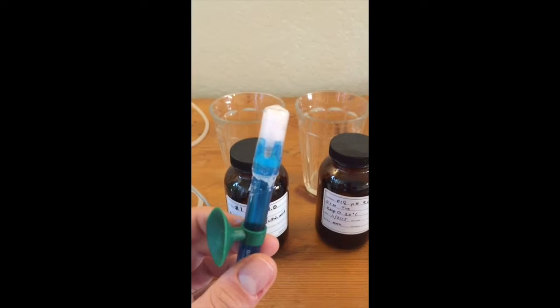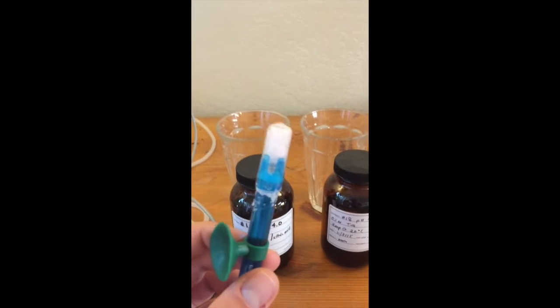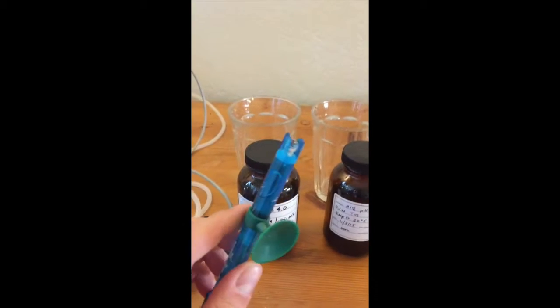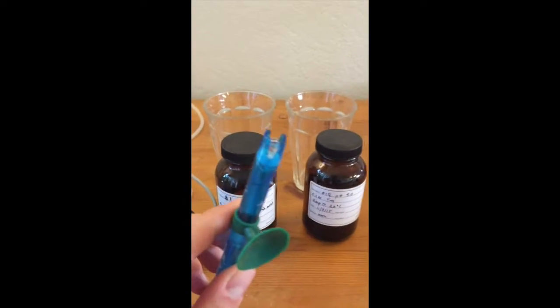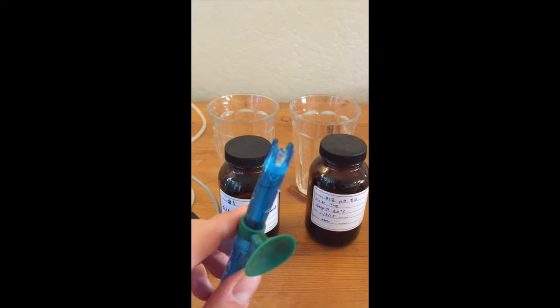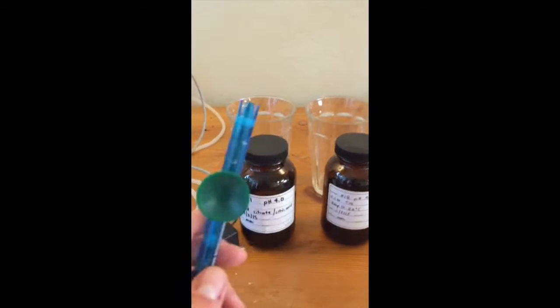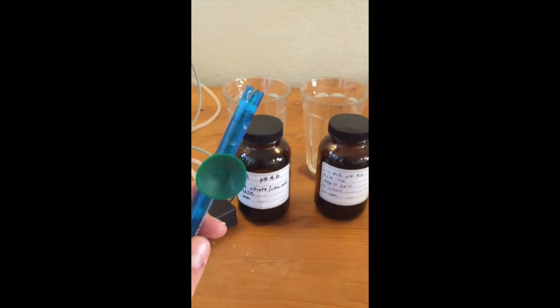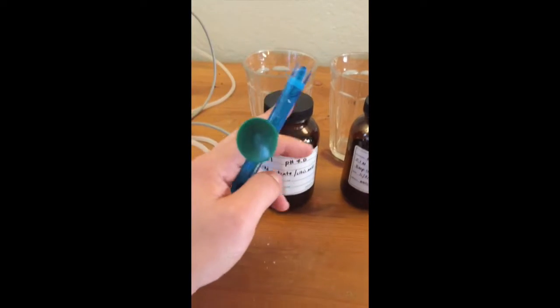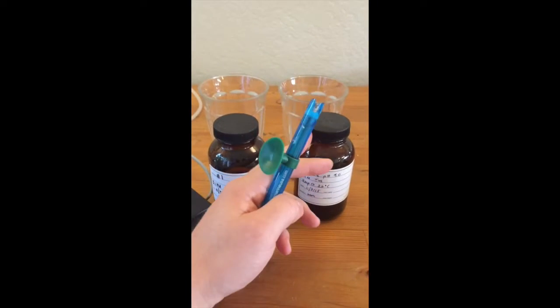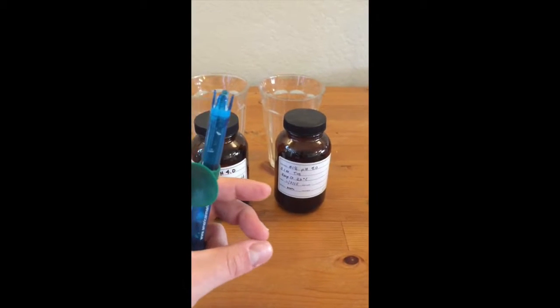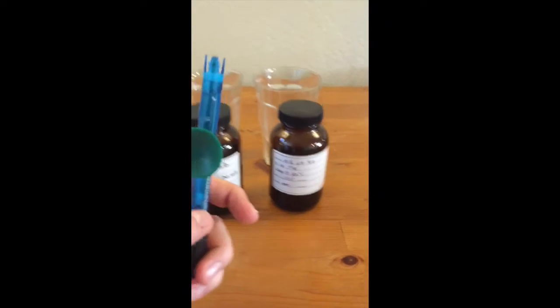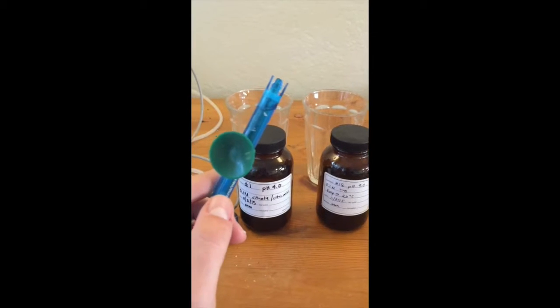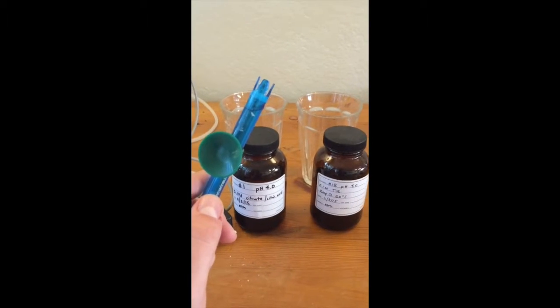Before you put your probe into your system, you want to remove this cap. Now we have the cap off. You can see this is the bulb itself, and that is what you use to read pH. To recalibrate, you need 2 buffer solutions. You need a 4.0, and you need something that's higher than 4. 7 is often a common one. Today we're going to use 9. You can even use the water in your system in an independent pH probe.